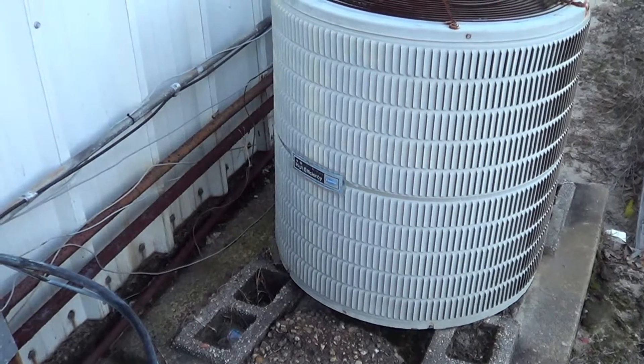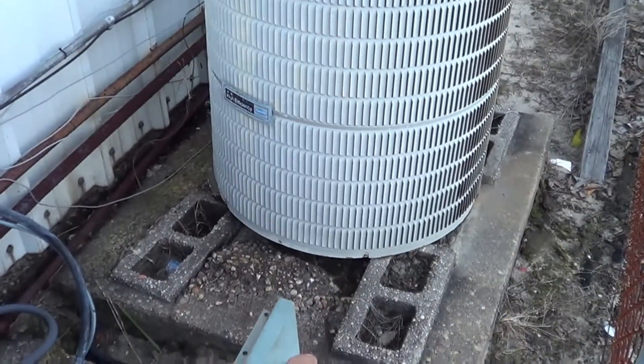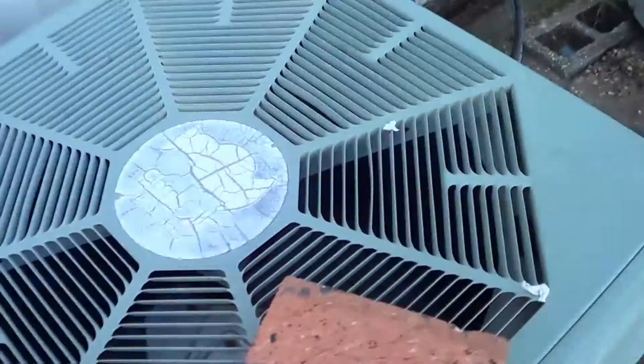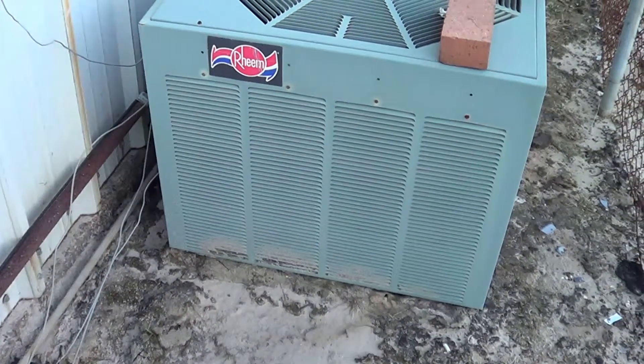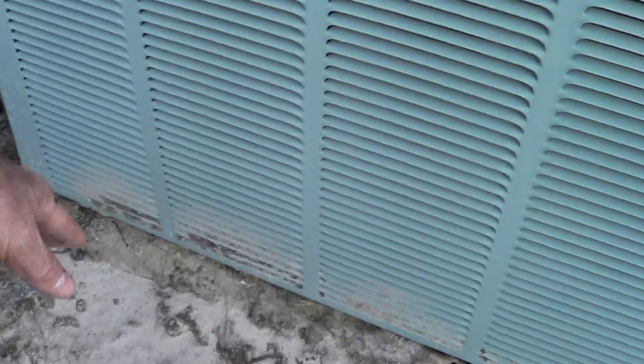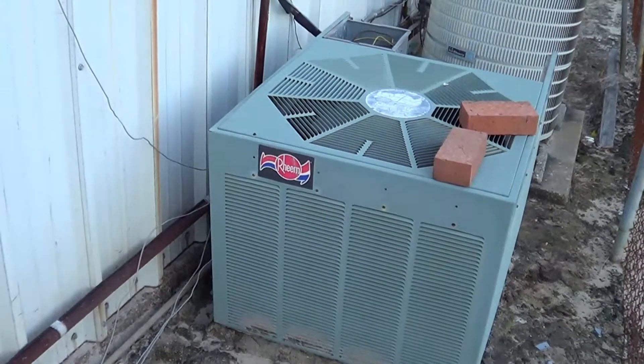With the Carrier unit here, it's lifted off the ground a little bit — that prevents dirt and junk from getting in there. On this Rheem here, they didn't put any objects under it. What happens is dirt comes down here, gets in the bottom end, and that's usually the bottom end of the coil which is the coolest part. It screws up the sub-cooling.